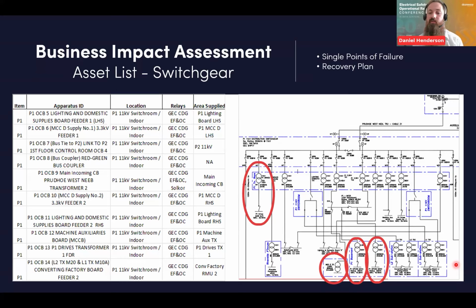As part of that, other considerations: I've got two assets here which are feeding single points of failure. But I know that in the event of failure there, the location of those LV switchboards is close to a roadway on site that's accessible. There are doors that can access, and I've got generator connection points at a very accessible level. So from that recovery plan, I know we can get a generator in there within 4 hours and the business impact will be minimal. I've got a single point of failure located in a basement area, which would be very difficult to get any generation to in the event of a failure, which would lead to a business impact. So that would be high up on my priority list.